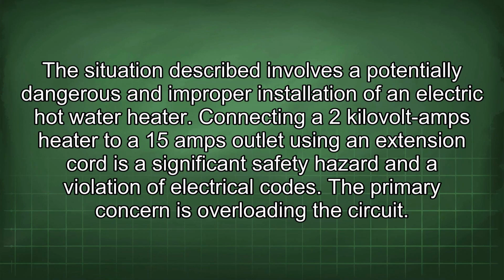The situation described involves a potentially dangerous and improper installation of an electric hot water heater. Connecting a 2 kVA heater to a 15 amp outlet using an extension cord is a significant safety hazard and a violation of electrical codes. The primary concern is overloading the circuit.